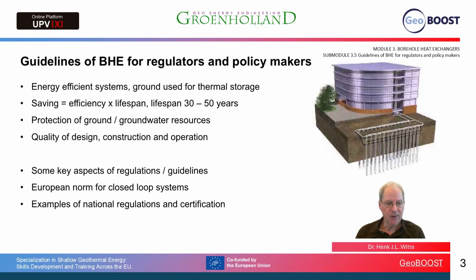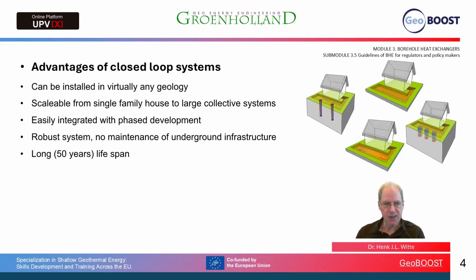We look then in more detail at the European norm for closed-loop systems, and at a certain moment we can go into, in different presentations, some examples of national regulations and certification. Now, advantages of closed-loop systems, of borehole heat exchanger systems, are that they can be installed in virtually any geology, that they're scalable from a single family house to very large collective systems, and can easily be integrated with phased developments of larger areas. It is a robust system. Once installed and properly tested, there is virtually no maintenance of the underground infrastructure, and at the same time, it has a very long lifespan, up to 50 years or something like that.